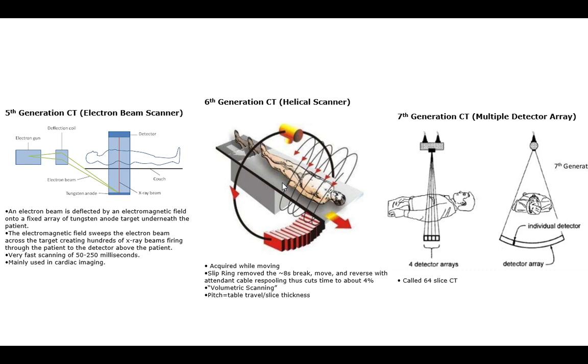I essentially deflect it and just scan the electron beam along so that it targets an angled piece of tungsten. So this is kind of like making this whole part, the left and the bottom half, essentially become one giant X-ray source. Heat problem's gone, right? Because your actual X-ray source is here, that midpoint along the ring. So I'm just targeting there.